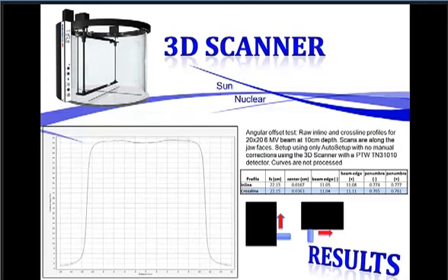I have had a very hard time getting this to look this well with any other tank and that's because most of the time that is user dependent and that is a flaw, at least in this user, in getting the tank perfectly straight to the jaws even with some of the nice auto setup routines that IBA has where it scans the beam and looks at the skew of the gantry. It doesn't always accurately predict how straight your collimator is. When we would scan these with our Blue Phantoms in the past, we would routinely see kind of like a wedging of the beam because you're scanning from outside the jaw and then you go across the face of the jaw. If there's any skew, you end up underneath the jaw. So you see this nice slope to the beam and that tells you whether or not you need to adjust your collimator or not. Whether it's consistent on both sides. If it's not consistent, then it's just the skew of one of the jaws.